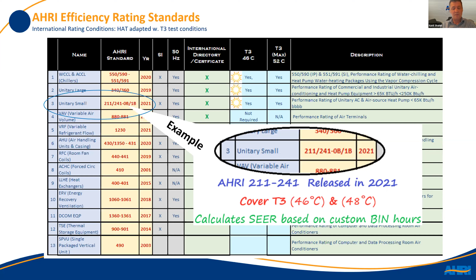This is a list of AHRI standards that cover high ambient conditions. A good example is AHRI 211/241, which is based on 210/240, covering all residential units up to 65,000 BTU. Consultants should require their products to be certified against this AHRI standard, as I mentioned earlier, to guarantee that specifications are met, along with other standards based on different applications.